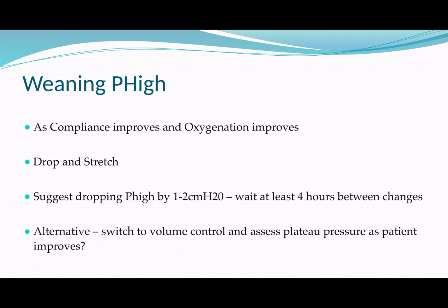You can do this in one of two ways. The most common way is the so-called drop and stretch. What this means is that you slowly drop down the amount of the PHigh by 1 to 2 centimeters of water every 4 to 6 hours.